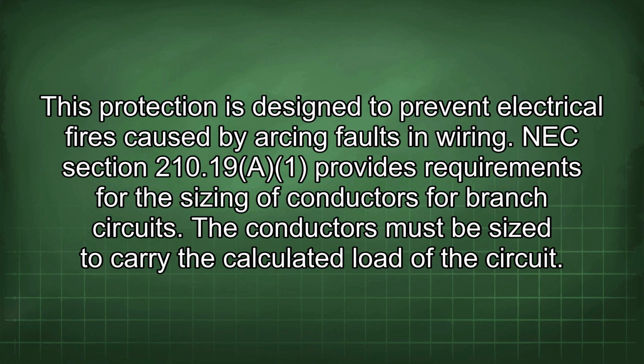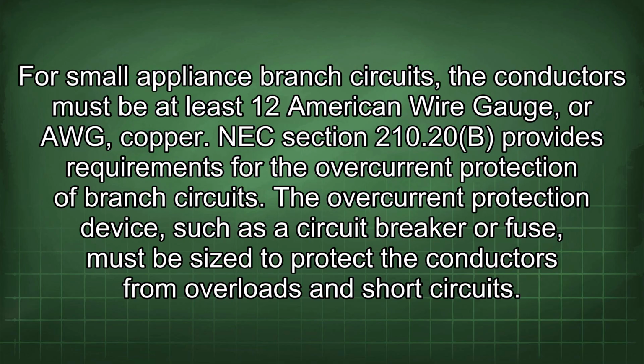NEC section 210.19(A) provides requirements for the sizing of conductors for branch circuits. Conductors must be sized to carry the calculated load of the circuit. For small appliance branch circuits, the conductors must be at least 12 American wire gauge, or AWG, copper.